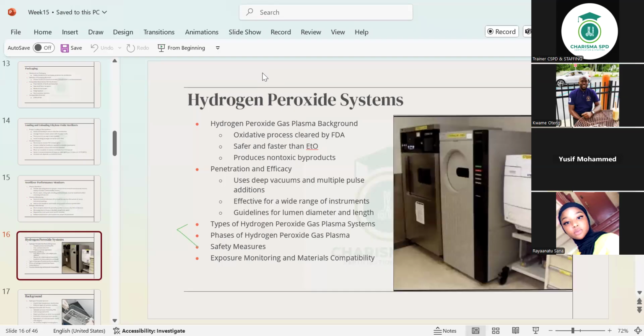The cycle and process involves vacuum, where there's heating, and then the injection, which is the second stage, where there's a pump of hydrogen peroxide into the vaporizer. Okay, and then the diffusion, which is more similar to the penetration in steam sterilization. The diffusion in the low temperature hydrogen peroxide is more like the penetration in steam sterilization. So the plasma, as we define, there's a vacuum that decreases the pressure, okay, and radio frequency energy is radiated within the chamber from the electrode screen.